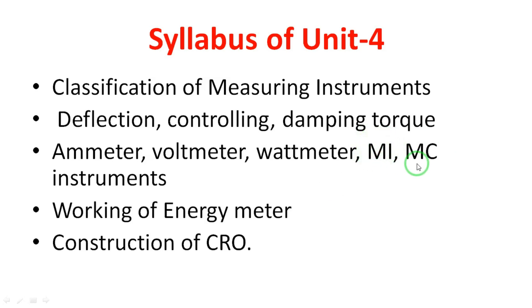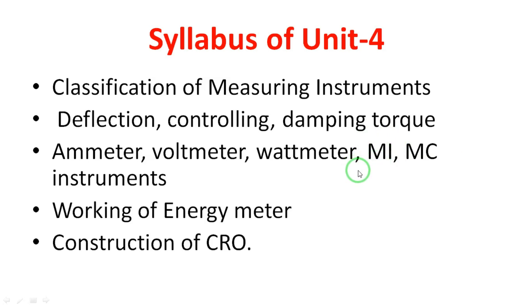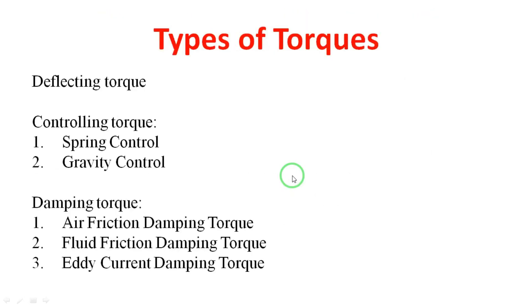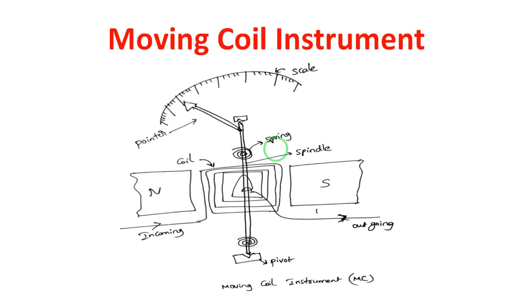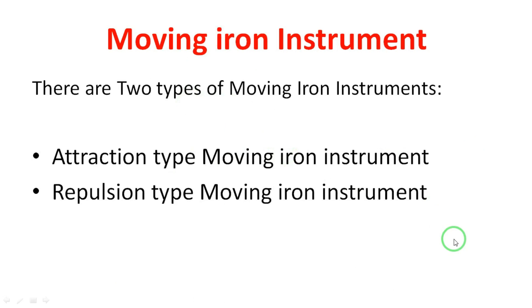Moving coil instruments are used for DC only, while moving iron instruments are used for both AC and DC. So moving iron instruments work with both AC and DC combinations. This is an important point. Now coming to the moving iron instrument — today we will discuss the moving iron instrument in detail.